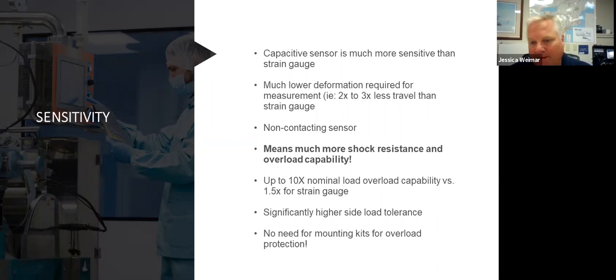So in addition, that heavier beam gives you more shock resistance and overload capability, which can be as much as 10 times more than the gauge is rated for. So in other words, if I have a 1,000 kilogram cell, I can overload that to 10,000 kilograms without damage. If I have a strain gauge system, typically it's 1.5 times operating load. Ours has a significantly higher side load tolerance. It can handle up to 500% of its rated capacity in a side load. So again, we don't need any mounting protection.